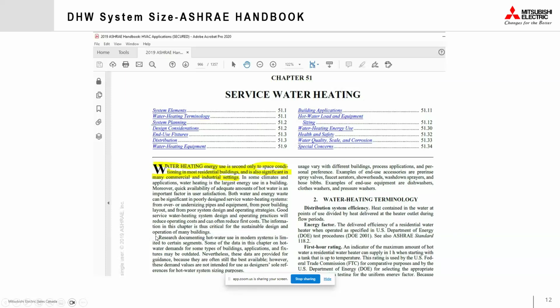The next resource is the ASHRAE Handbook, chapter 51, which gives you the guidelines, especially for sizing domestic hot water and how it rates the type of building as low, medium, and high. The occupancy of the building and all those factors are connected, and then you can find out how many gallons per hour per day of domestic hot water are needed.